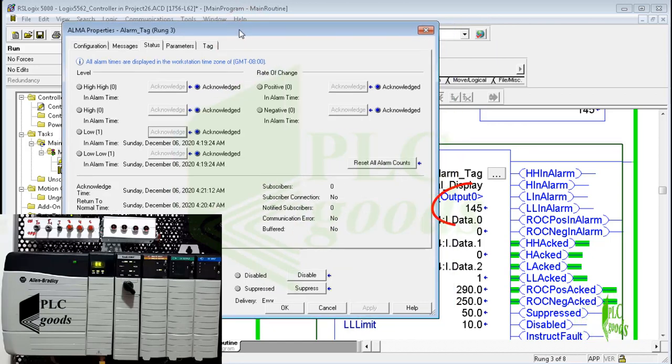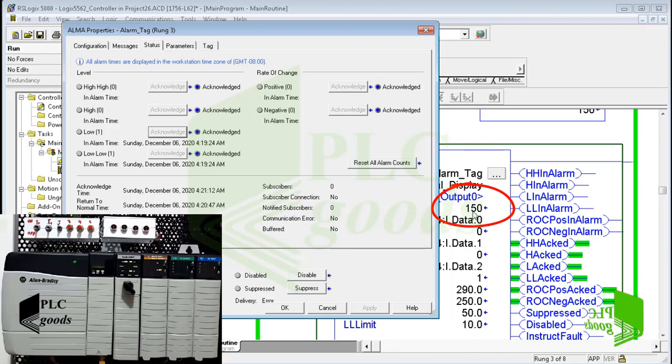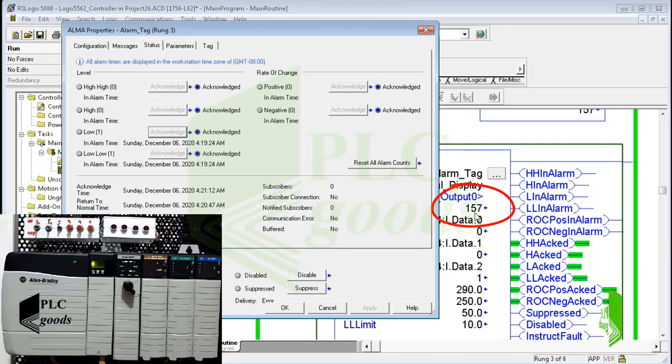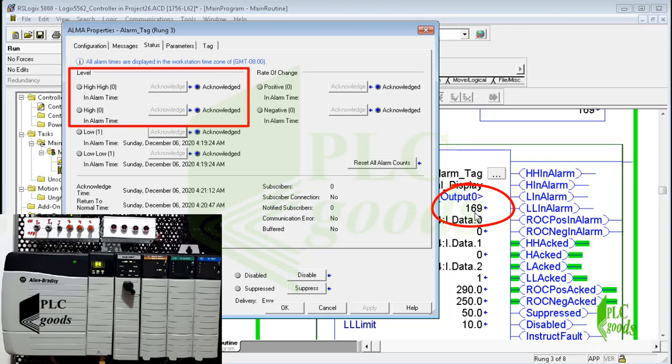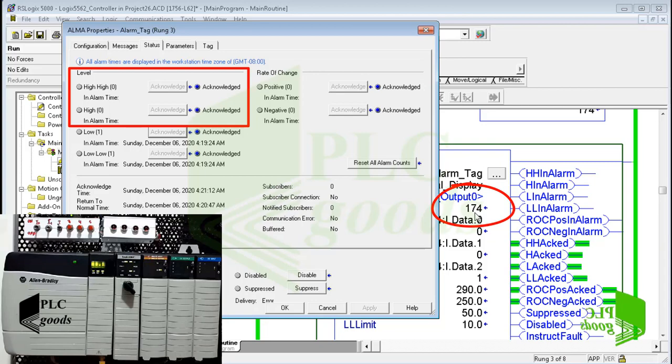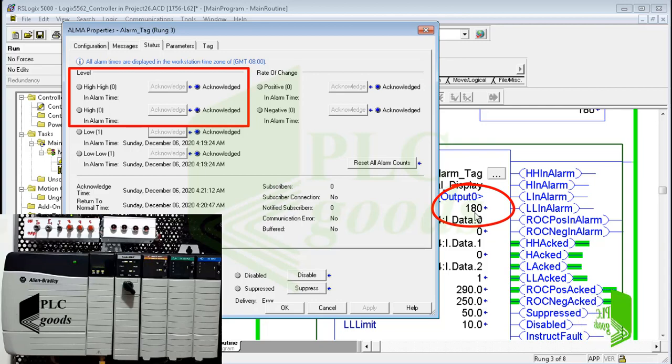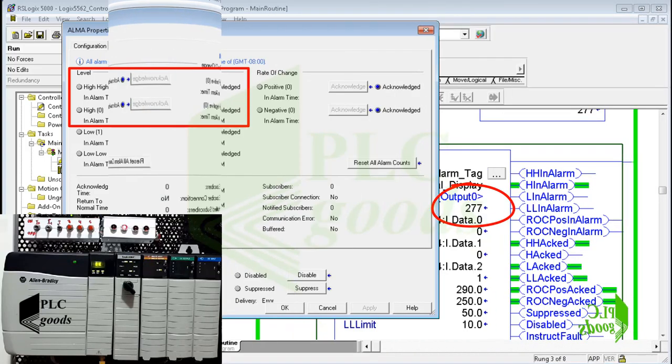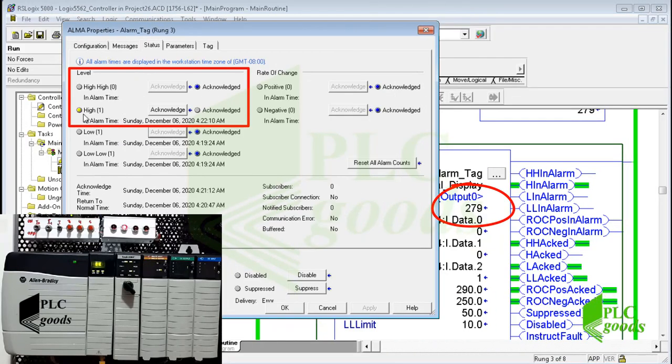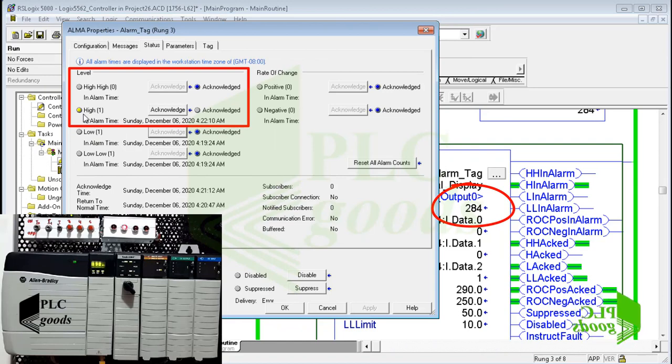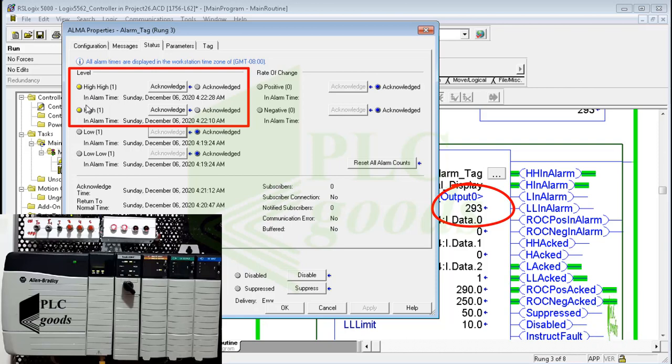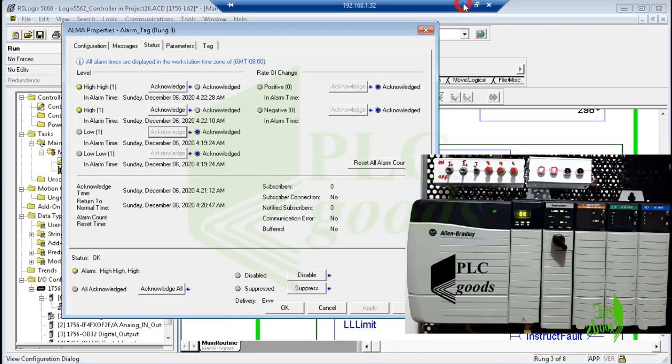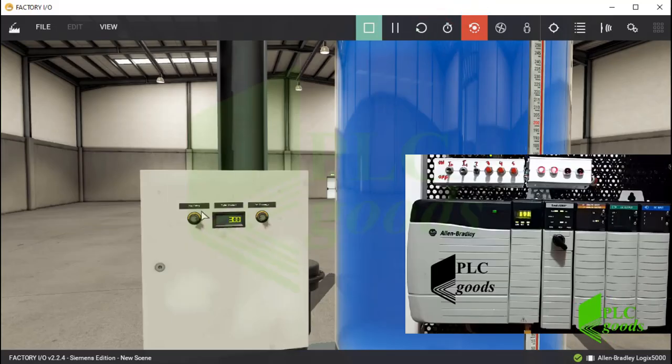Now let's wait to raise the water level to 250 and 290 centimeters. It's expected two other alarms related to high water levels will turn on the two first digital outputs respectively. Well, two alarms related to two high water levels have been activated. Now the tank is full.